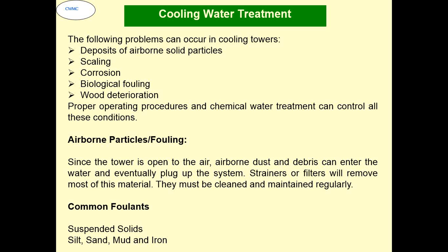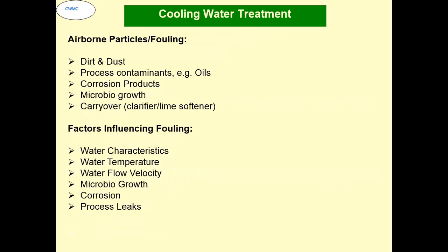Airborne particles fouling: since cooling towers are open to air, airborne dust and debris can enter the water and eventually plug up the system. Strainers or filters will remove most of this material. They must be cleaned and maintained regularly. Common foulants are suspended solids, silt, sand, mud and iron. Airborne particles fouling also includes dirt and dust, process contaminants such as oils, corrosion products, microbial growth, and carryover from clarifier, lime softener. Factors influencing fouling are water characteristics, water temperature, water flow velocity, microbial growth, corrosion, process leaks, and of course the airborne dust, which also constitutes a major source of fouling in the cooling water system.